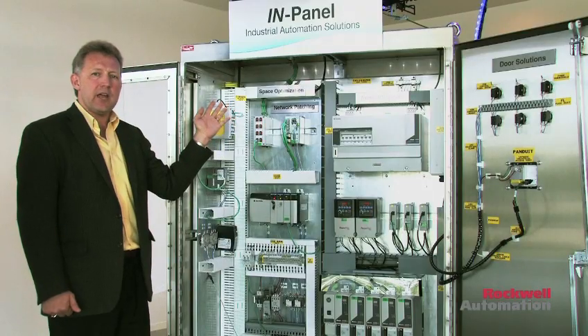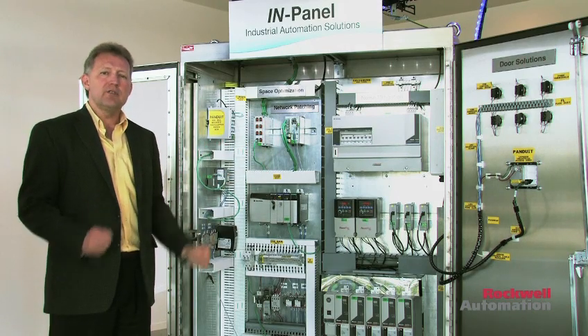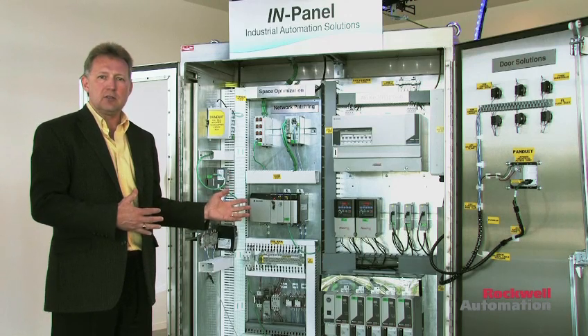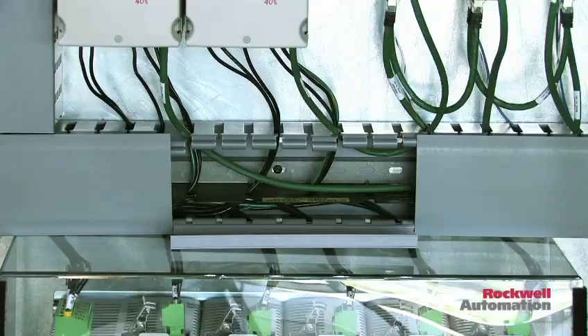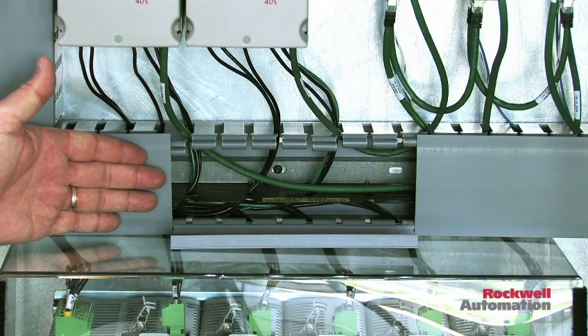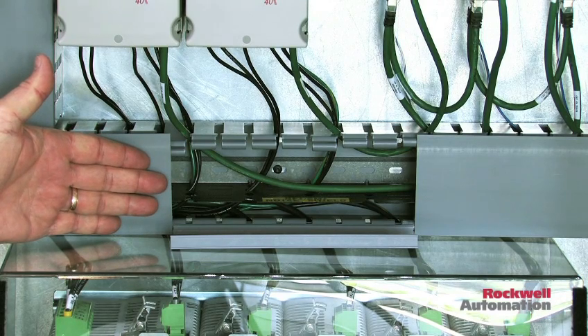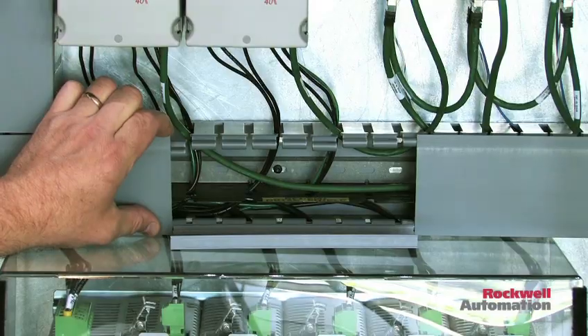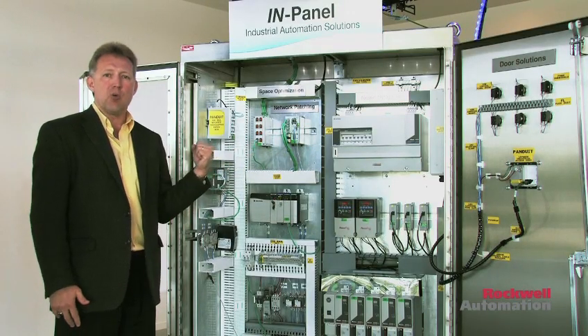Panduit also has a wide range of space optimization tools to help shrink control panels. This is very important for an equipment builder as they move from standalone control panels to on-machine control panels. Space optimization includes tools like the shielded ductwork, where noise dissipates at the square of the distance as far as spacing cabling. You're now able to reduce that space, have clean, dirty, and very dirty cabling closer together, but basically mitigate that noise in an overall smaller control panel design.